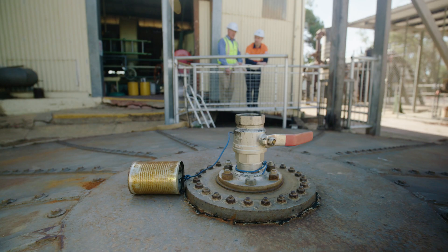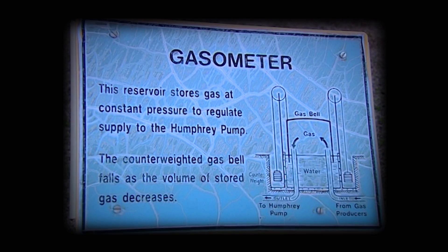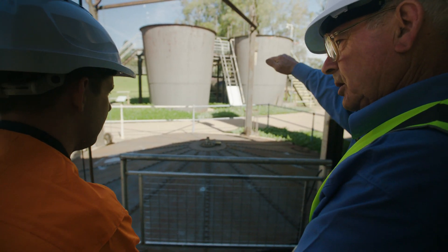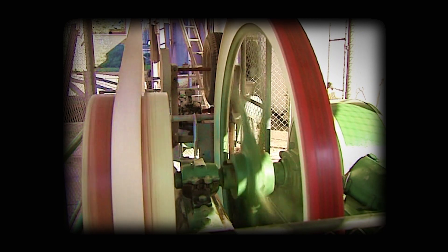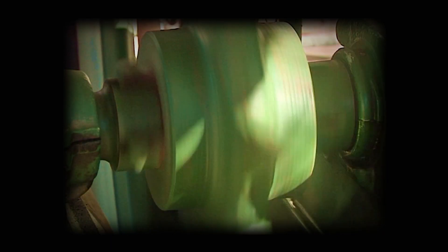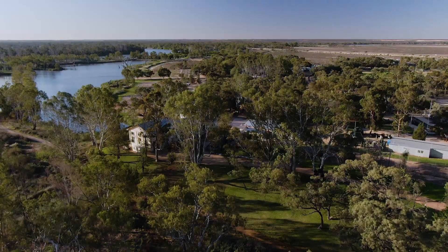This is the gasometer. We use the valve in the middle — you open that valve to let any air out, so that the gas can come through into the gasometer. Any air comes out there, so you've got good gas in the gasometer. Then when you've got good gas, you can shut that off, and then the gasometer will rise out of its container and put pressure on to go inside into the Humphrey pump. The next thing we do is start up the old gas engine over here, the old Crossley. We fill the gasometer up and then oil up the old Crossley gas engine. We drop the compression lever here, and if the gas is good — chook, chook, chook — and away you go. And that drives all the auxiliary power that we require inside the pumping station.